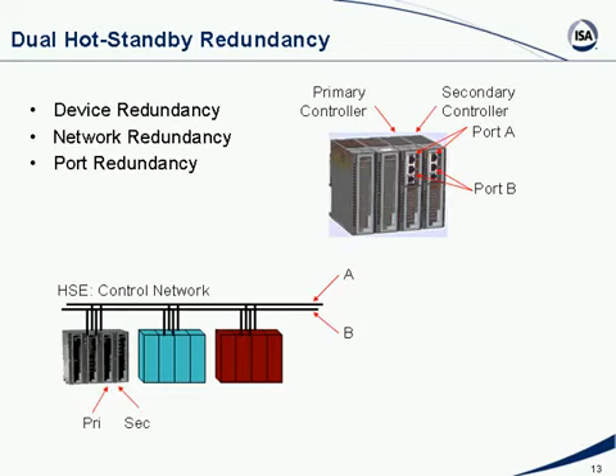Redundancy is something deeply ingrained in all of us engineers whenever we talk about communication. It's drummed into us since we started our careers - there has to be redundancy. Definitely when you talk about control networks, the Ethernet connecting all the controllers together, you need it, because it carries a large volume of data shared by the whole system. So it needs redundancy to eliminate single points of failure.